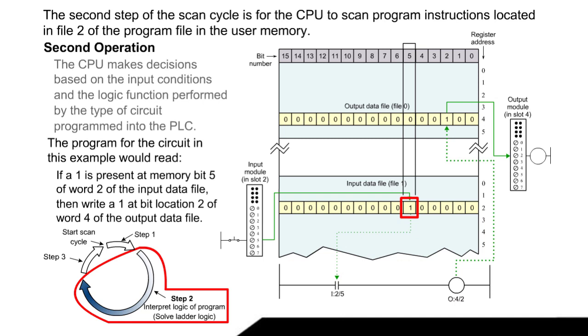The program for the circuit in this example would read, If a 1 is present at memory bit 5 of word 2 of the input data file, then write a 1 at bit location 2 of word 4 of the output data file.